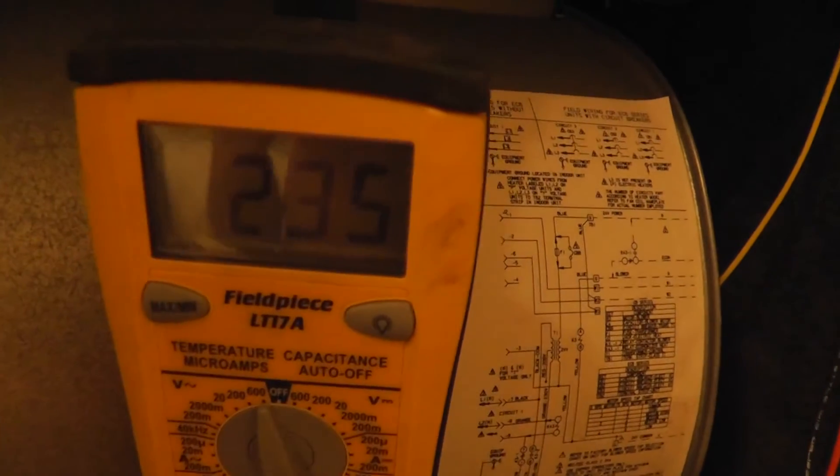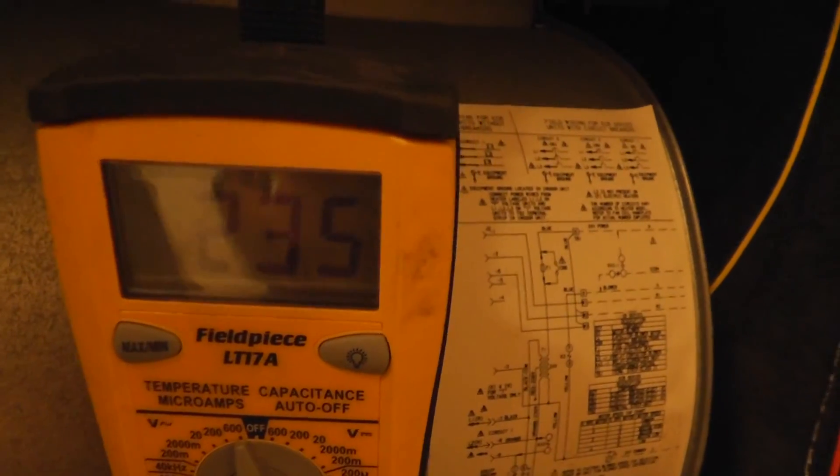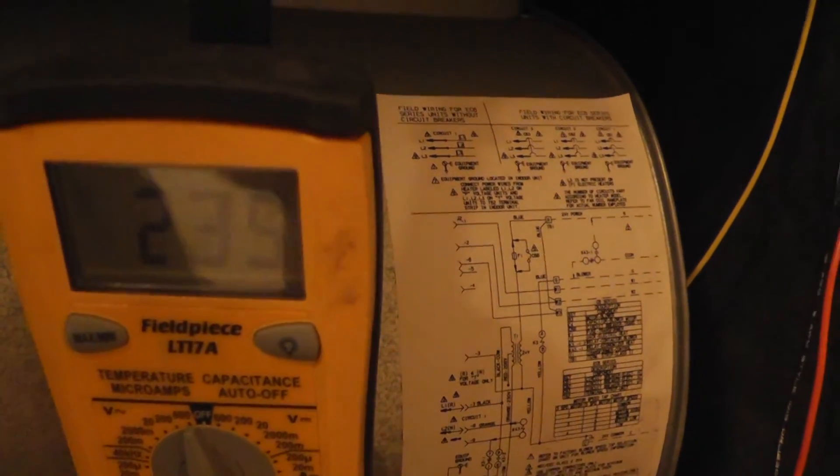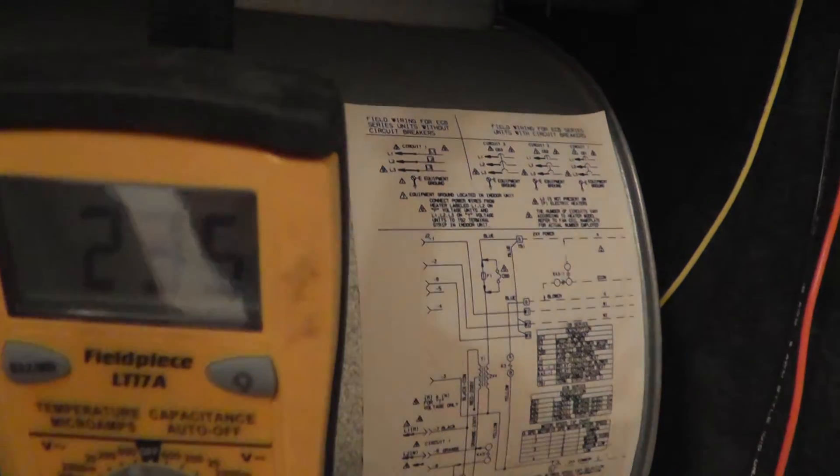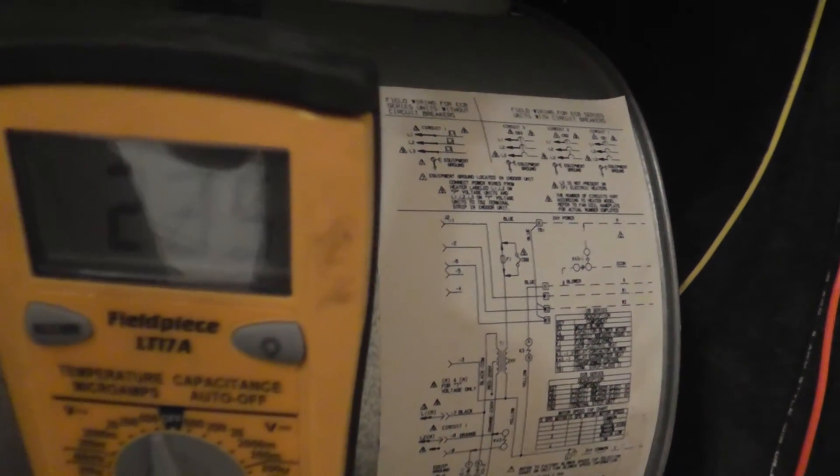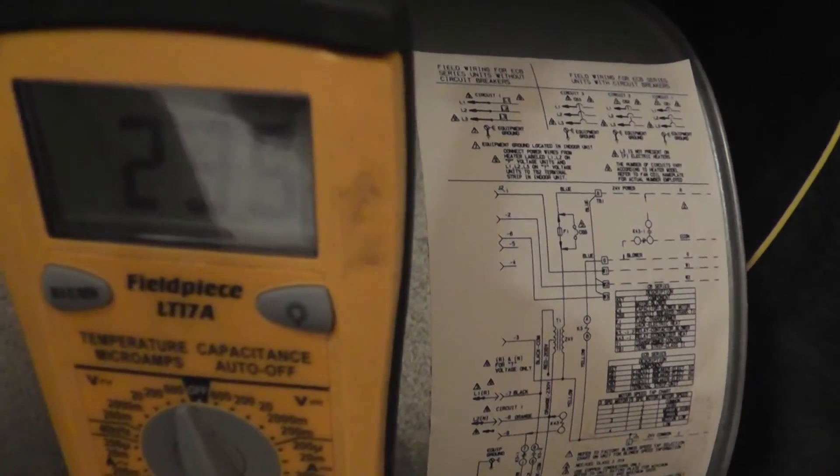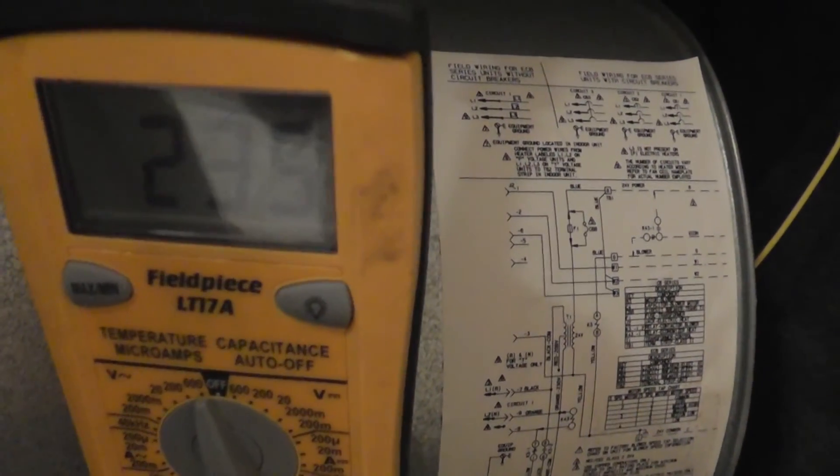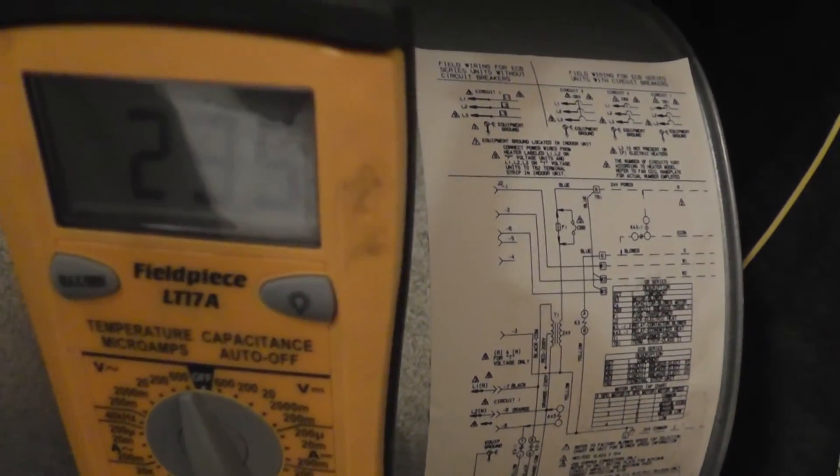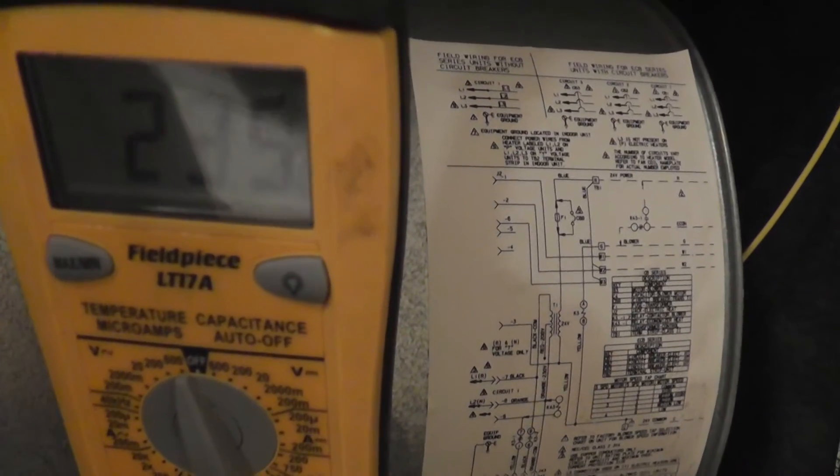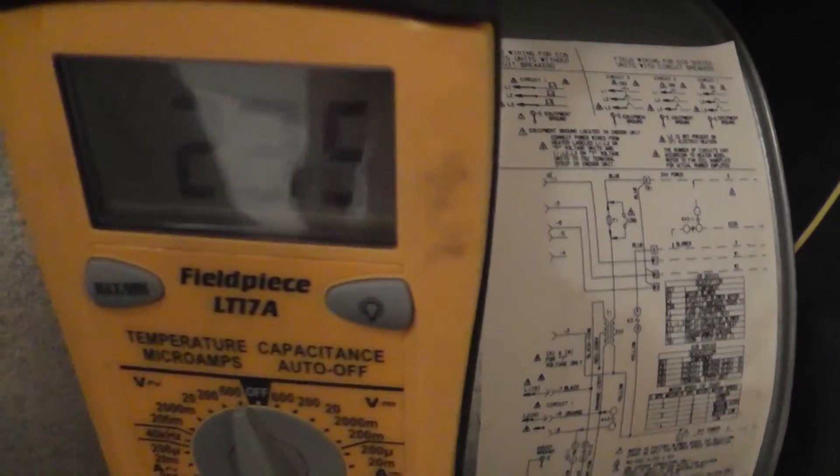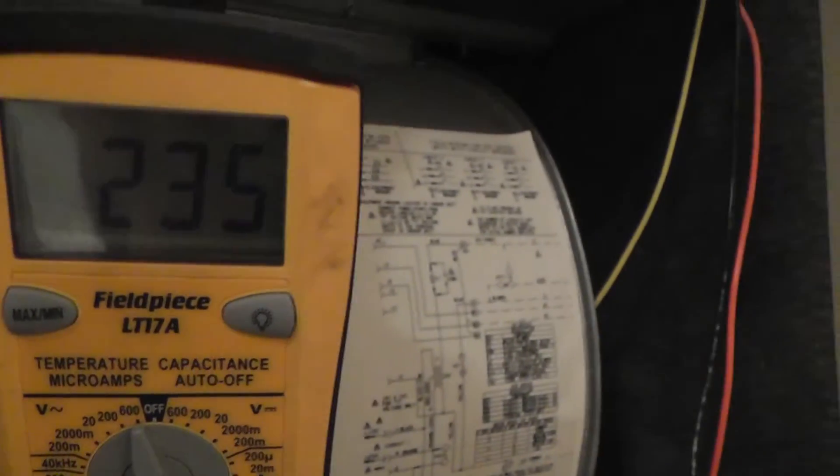What do we get there? Boom. 235 volts. We're looking for about 230 to 240 volts. Bingo. Right on the money. So we do have voltage at the motor where it's supposed to be getting voltage. So what's that? That means the motor is bad. If the run capacitor is good, that means the motor is bad.